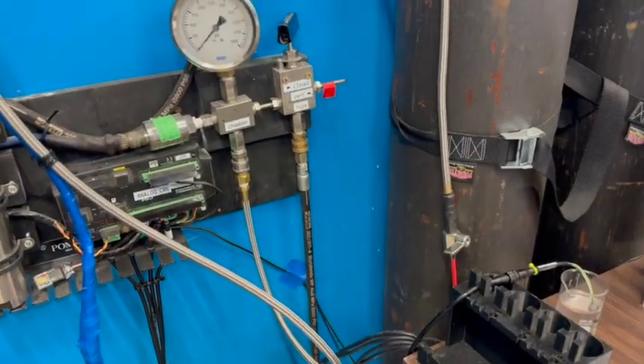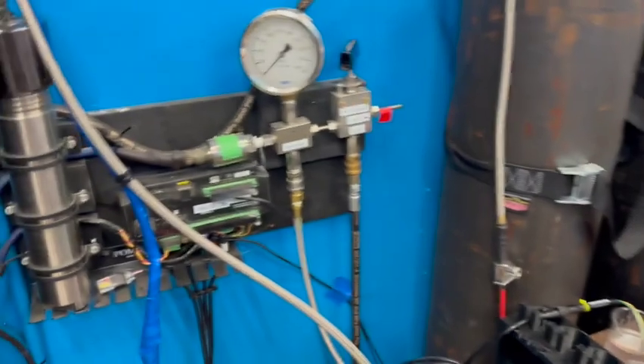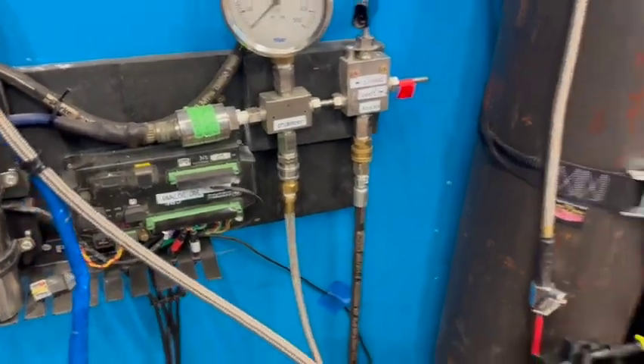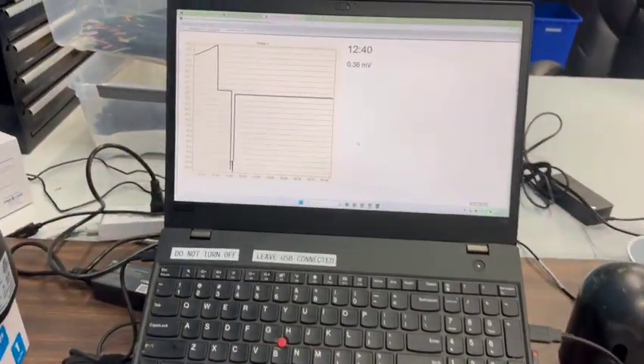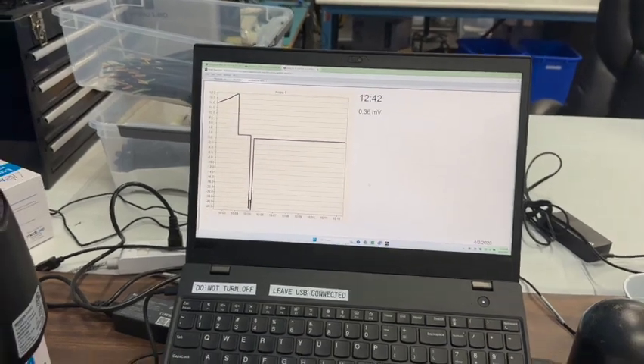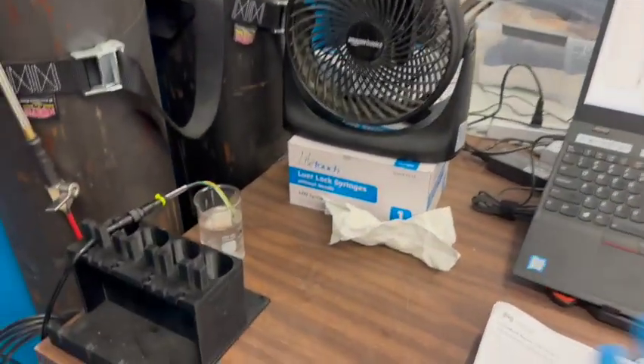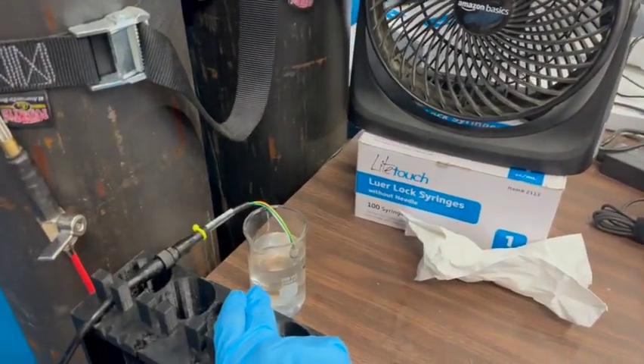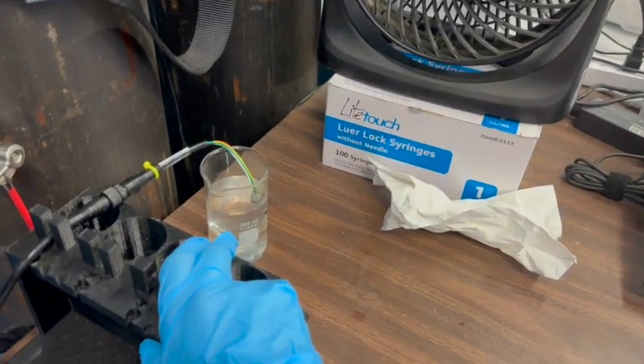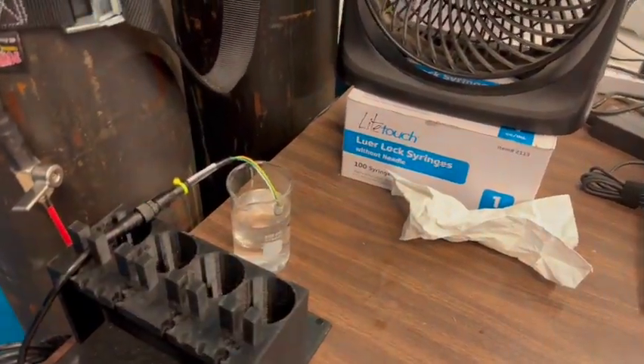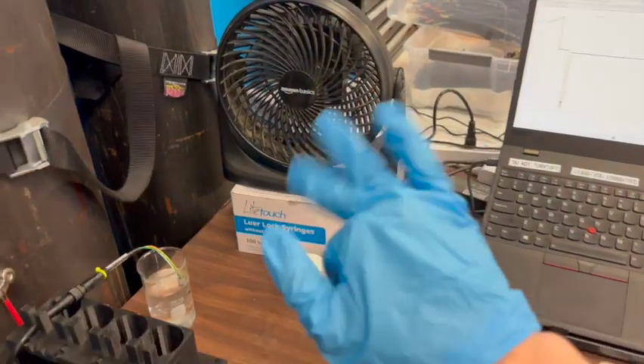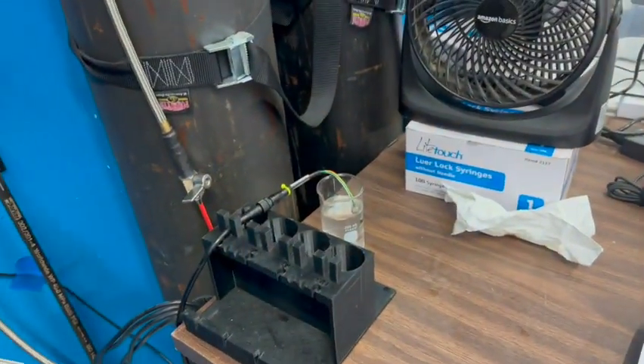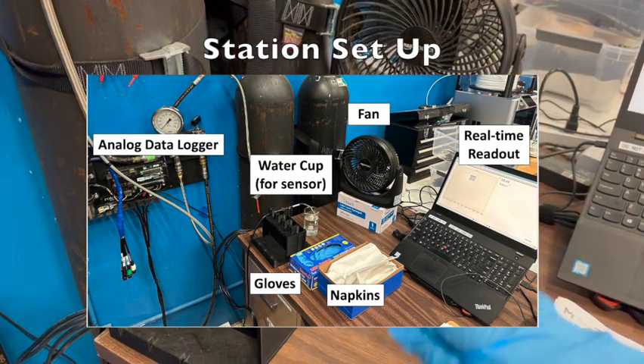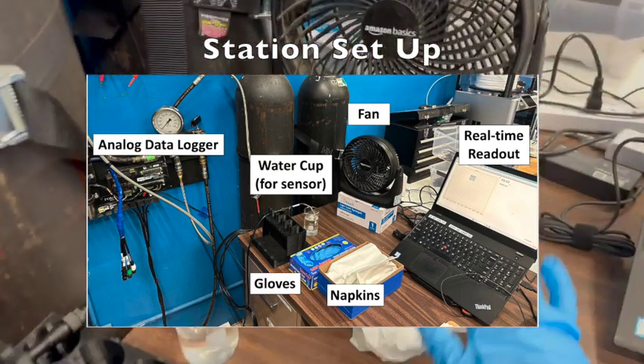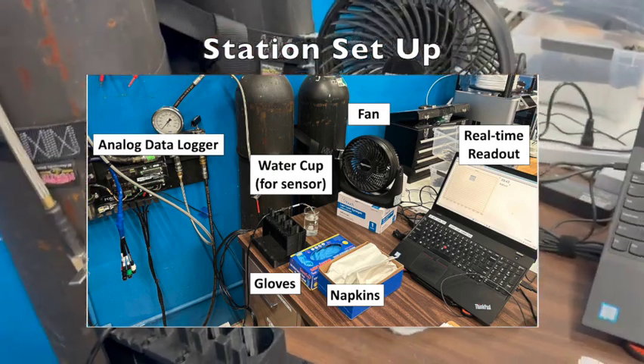Okay, so for this test, you'll need a data logger that connects to a real-time readout, like this one here. It's refreshing. I have my sensor here in water, and it's been in water overnight, and I've cleaned it off as much as possible. I also have a fan going, and that'll help the sensor dry out. I'm wearing gloves to prevent contamination, and I have napkins to dry out the sensor.